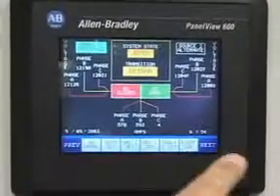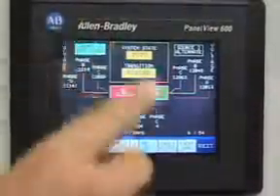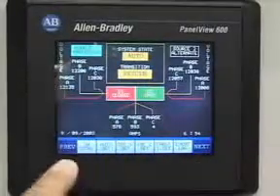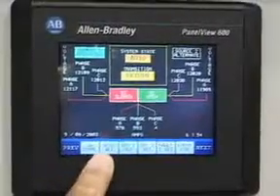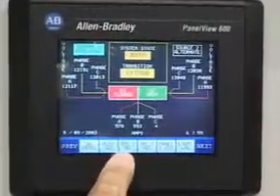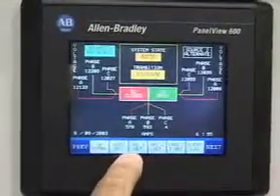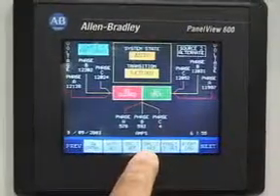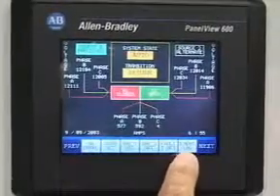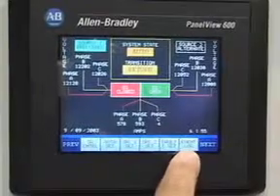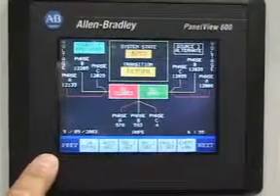Look at the bottom menu, and it shows all the screens we have on this panel view. The status screen that you're looking at now will not be lit when you're on that screen, but it shows the screens that are not lit at this time. Switch control, your settings for your automatic, your source 1 setting, which is the parameters for voltage pickup, dropout, verification timer, etc. Source 2, the same settings as source 1, and then fault blocking settings, and then we have an event log, which records all the actions that the device has taken for the last 45 operations. Let's go to the switch control screen now.